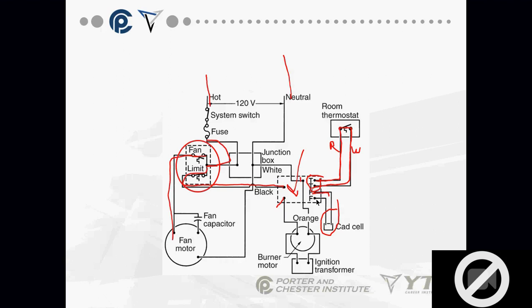So, is this fan limit switch all 120 volts, or is it a split between 120 and 24? All 120? Yeah, all 120. It's a dry switch, right? Well, I don't want to say it's a dry contact, but it's all 120. Now, what happens if that limit switch opens and the customer has a digital thermostat without batteries?